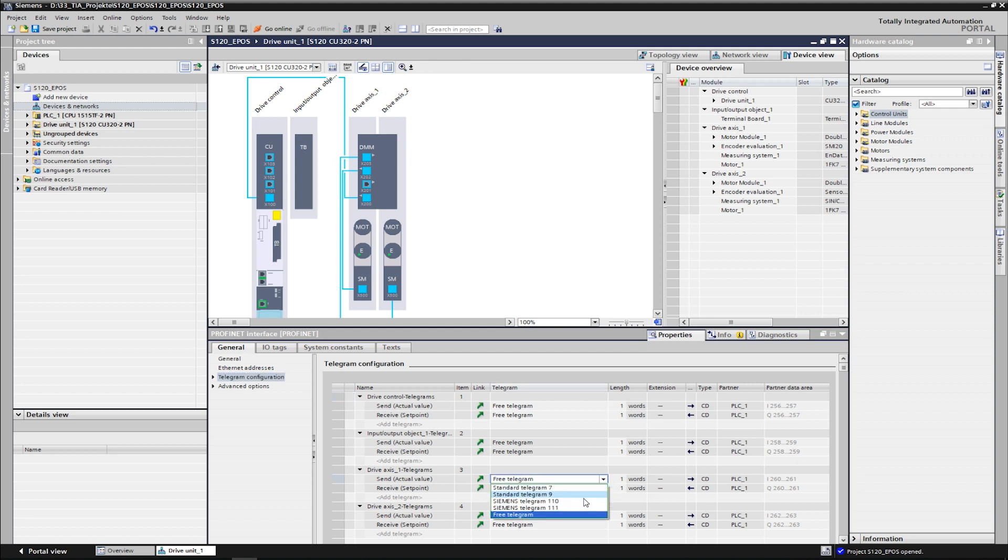After the function module basic positioner is active on the first axis, only the telegrams for positioning are available. The SinaPos block requires the telegram 111. This telegram is selected and adopted for the send and receive direction.